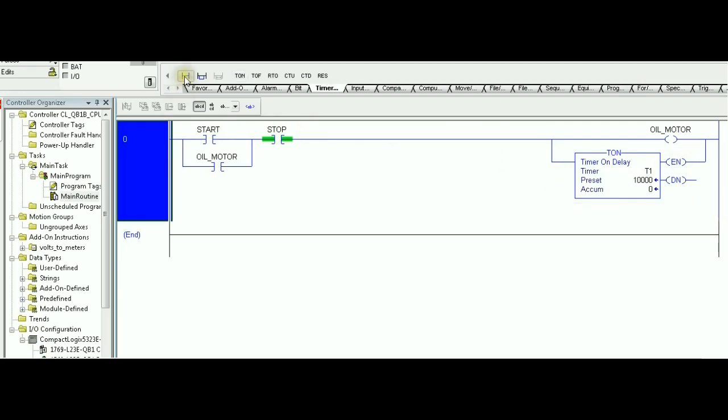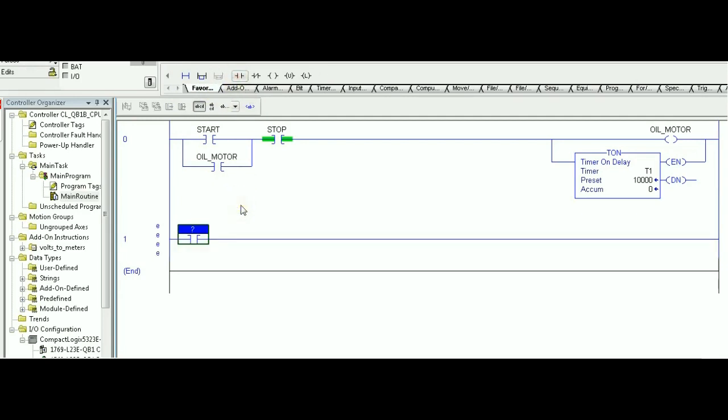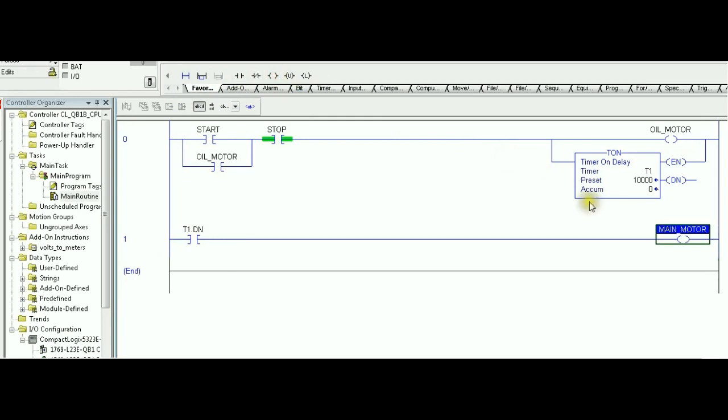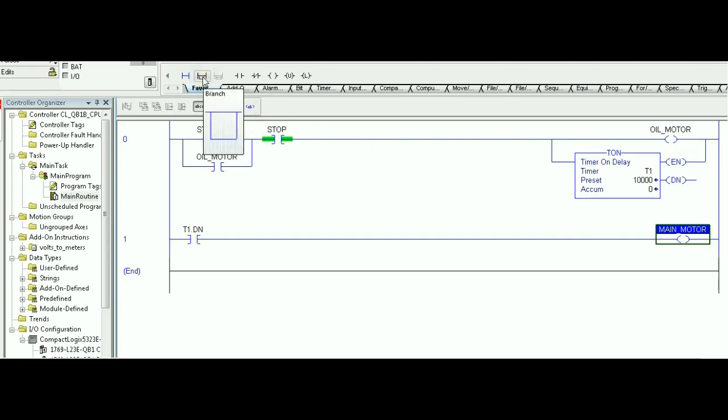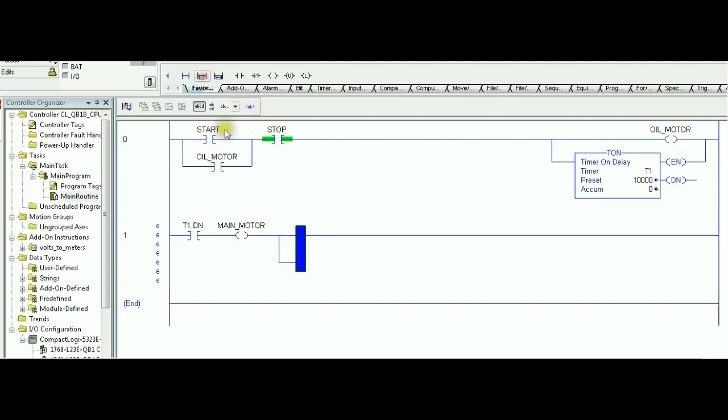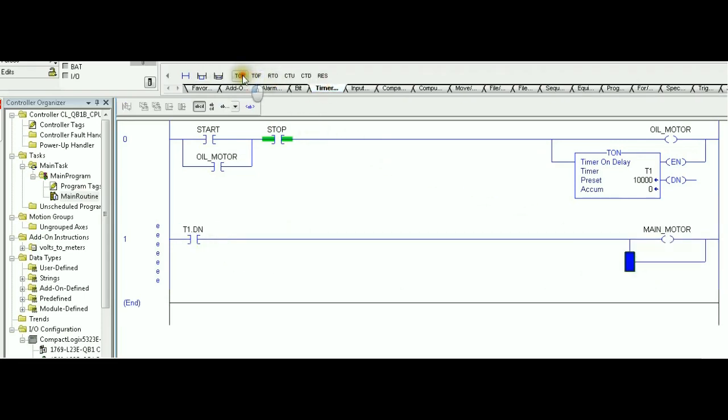In the second rung, what we are going to do, we are going to make use of the done bit of the timer to start the main motor. So, start, trigger the oil motor with the timer. 10 seconds later, the main motor will be on. But there is one more requirement, which is a five-second delay after the main motor is on. So, similar to the first rung, I'm going to create a branch parallel to the main motor.